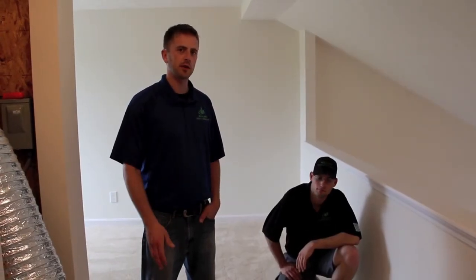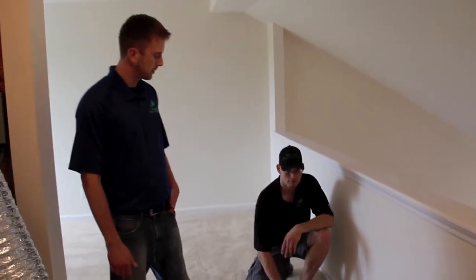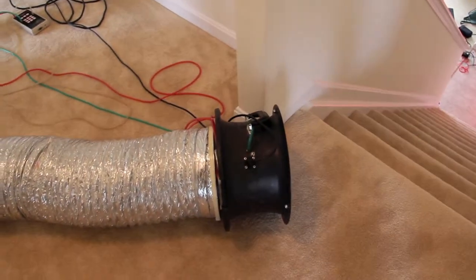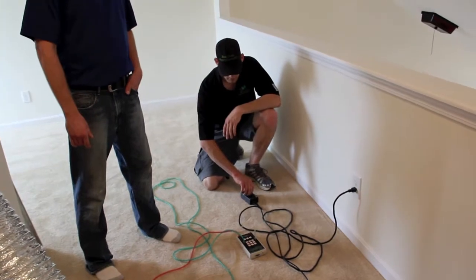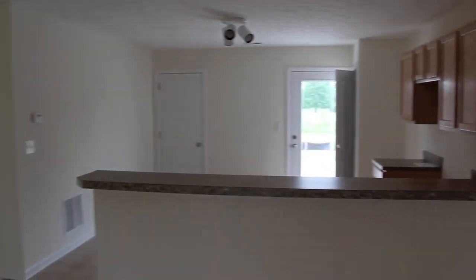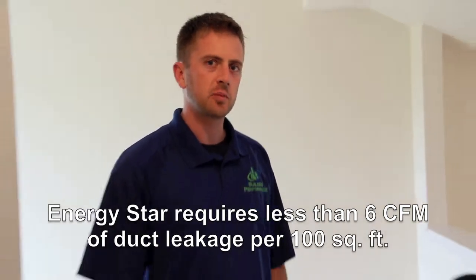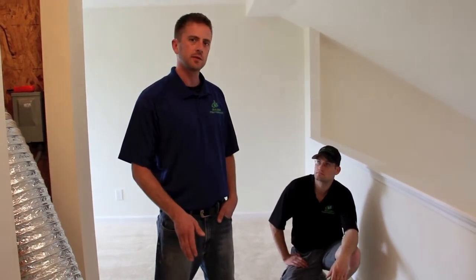We've got the blower door set up and it's simulating air leakage on the house again. We're ready for our duct test, and Sean's going to turn it on and see what kind of numbers we get. It looks like we've got about 45 CFM of duct leakage to outside, which is within ENERGY STAR standards — so this house actually passes. But we still need to check the attic for insulation depth and quality installation, get some model numbers, and we'll be finished with this inspection.